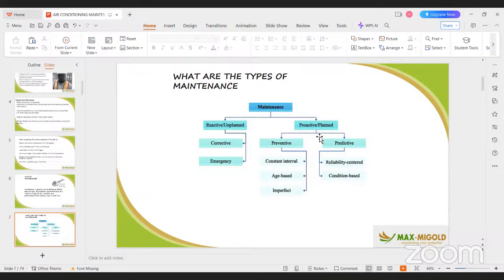Then the other one is what they call predictive. What does predictive do? In predictive maintenance, you look at a particular graph. Those of us who are engineers take data from the equipment every day. You go to multinationals and see they take the value of temperature, pressure, and the quality of the indoor unit, and plot it against a standard graph by the manufacturer. Once they see a deviation, the temperature was supposed to follow a certain path but it's moving away from standard practice, you know it's time for maintenance.